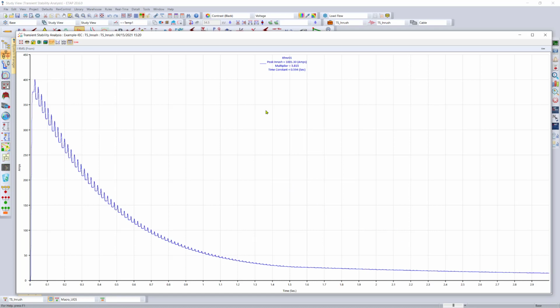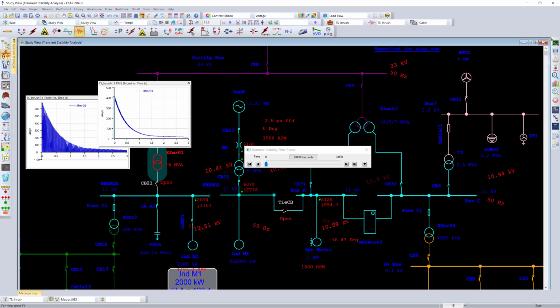So with this, you can deliver your grid code compliance study, which may be related to a flicker in the system due to transformer magnetization, and not spend too much time trying to interpret these values from the actual inrush response.